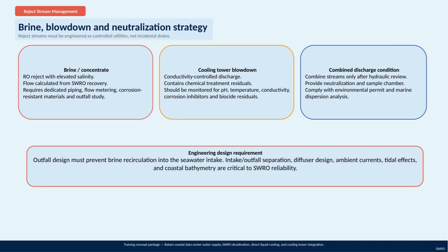When we talk about reject stream management, it's crucial to understand that these streams, like brine, blowdown, and neutralization, aren't just incidental drains. They need to be treated as controlled utilities, engineered carefully to manage their environmental impact effectively. Starting with the brine or concentrate from the SWRO process, this reject has higher salinity, and the flow rate depends on the SWRO recovery.